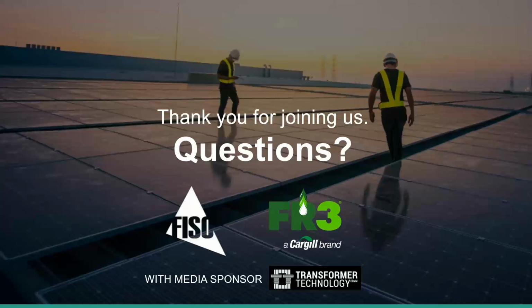So that was possible. Just adding one piece of information, Professor. During the development of the bushing electrode for this 420 kV unit, the type tests require increasing the voltage class up to 2 levels. So we had the bushing electrode being tested to the level of 2050 kilovolts impulse. That would be the first level of basic impulse level for a 765 kV AC. So we had tests going all the way up to 2000 kV impulse.